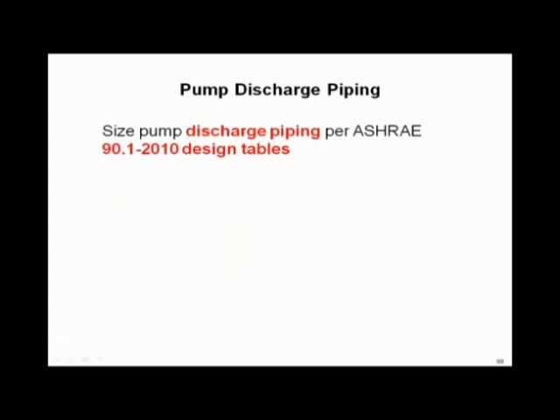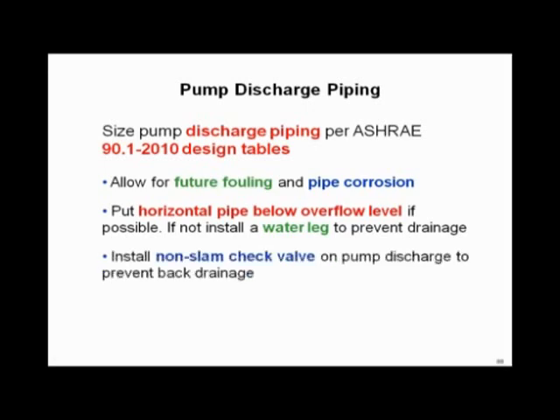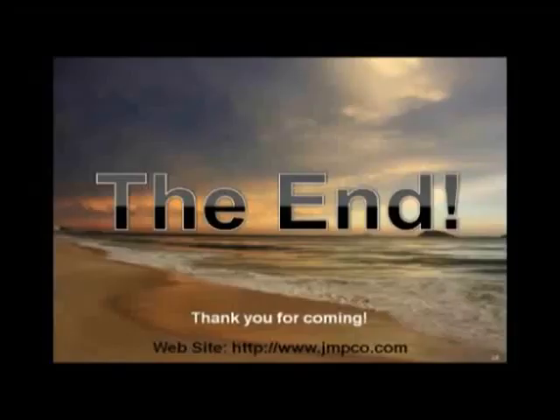Now, let's look at a little bit of discharge piping. First of all, you saw that ASHRAE 90.1-2010 now defines the minimum pipe sizes on condenser water piping. So you might as well get used to it. You do need to allow a little bit for future fouling and pipe corrosion. What's the reasonable number? You decide. Five to ten feet safety factor is what I see people normally doing. It is reasonable to assume that an open system like a cooling tower, that the piping over its pipe life is going to foul some and you will pick up a little additional pressure drop. If you've got horizontal piping as we showed you in that drain down thing, make sure there's a water trap or it's below the tower. And we'll look at that picture again in just a minute. Make sure you've got non-slam center-guided check valves in the discharge of your pump. You want to make sure they don't leak back. You've got to make sure you've got good quality check valves. You can install a pipe filling line above the check valve if you're worried about trash, so you can keep everything primed. Thanks for tuning in. Have a great day.